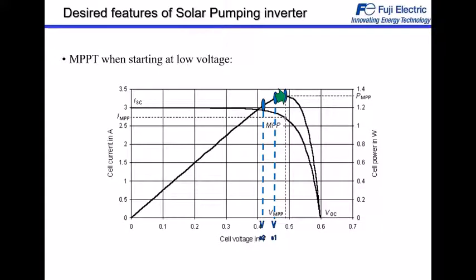It continues the operation in the opposite direction and recognizes there is more power, more power it can get from the panels. Of course, we need 3 points to see if this is the best point. So it moves again, increases the voltage, and now gets less current, less power. It recognizes this, goes back, and stays at the point of maximum power.